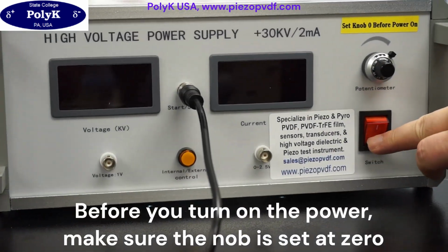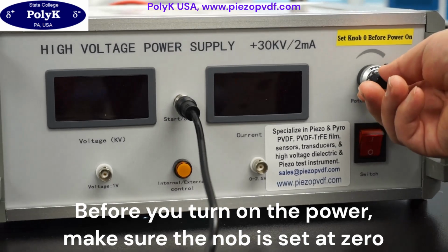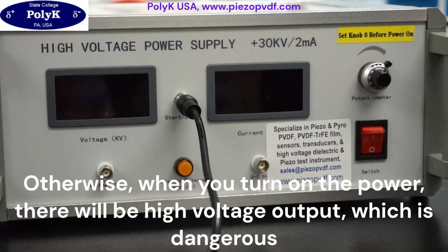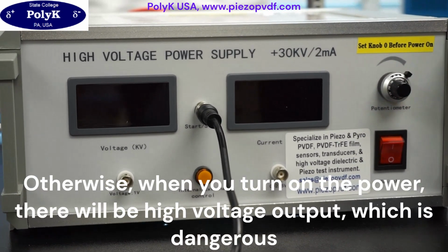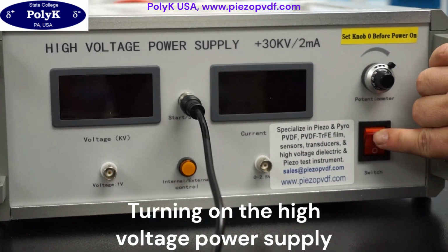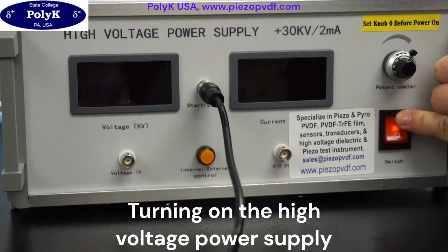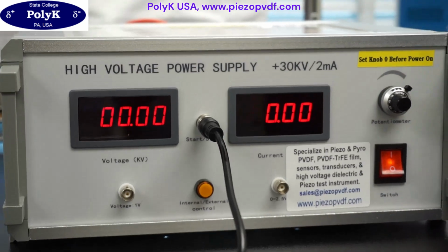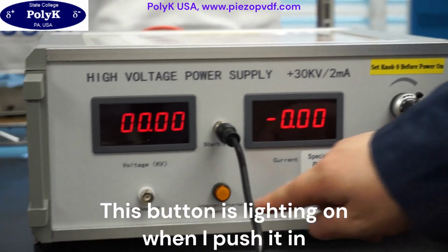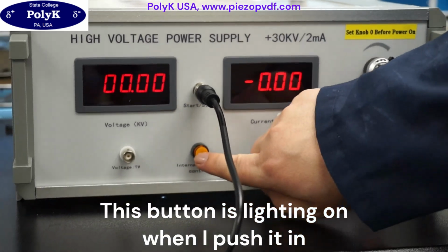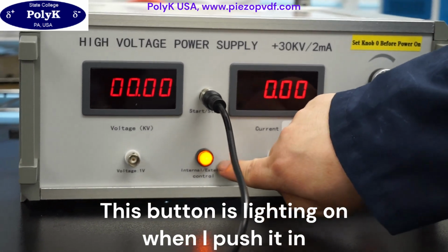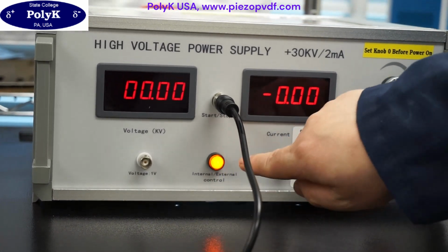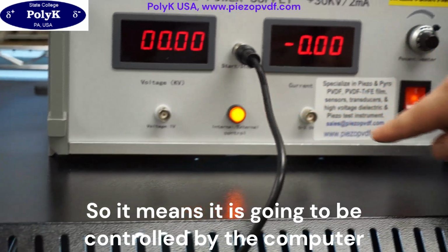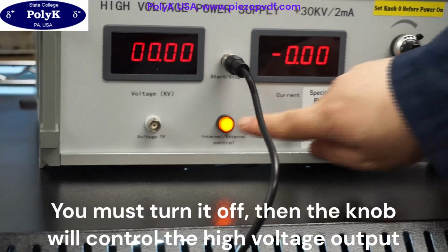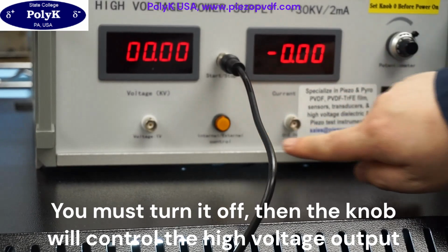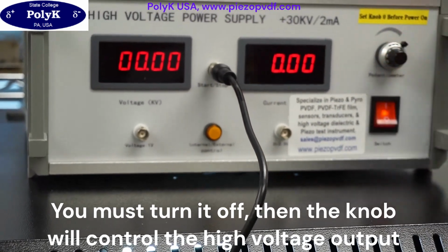Before you turn on the power, make sure the knob is set at 0. Otherwise, when you turn on the power, there will be high voltage output, which may be dangerous. Okay, and I can turn on the high voltage power supply. It's on, and this knob, if I push it in, it's a bright color, right? That means it's going to be controlled by the computer. The knob will not work. You must turn it off. Then the knob will control the high voltage output.